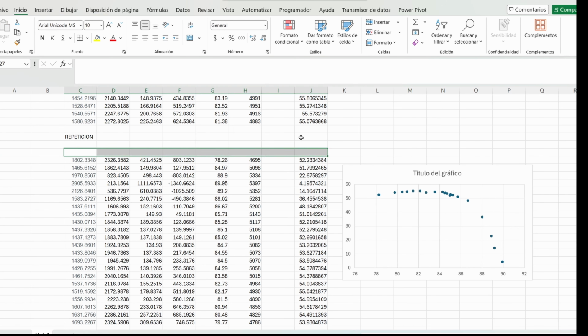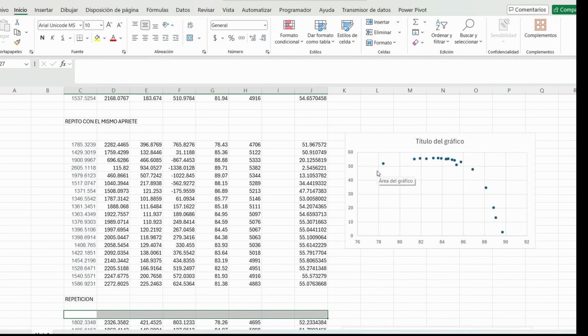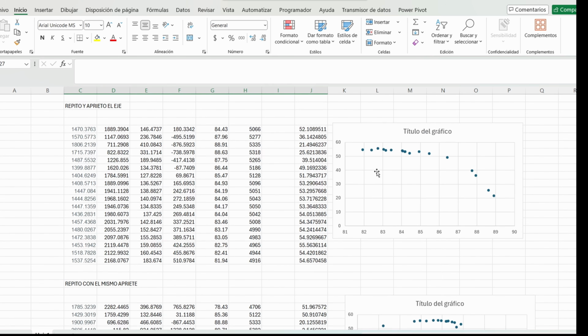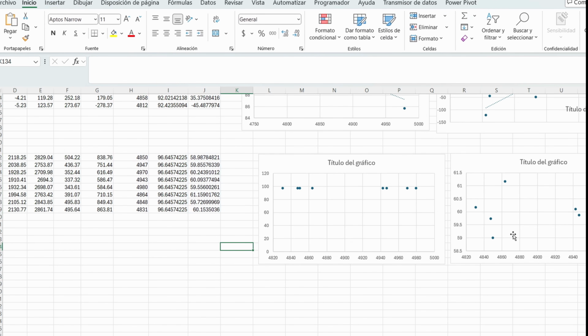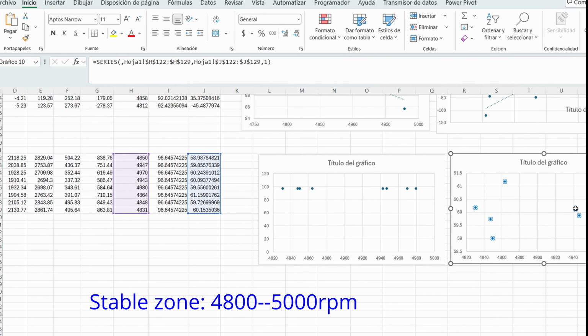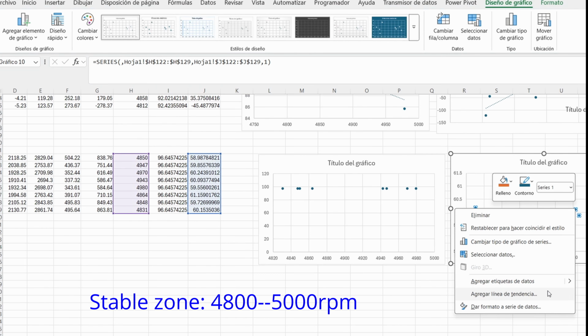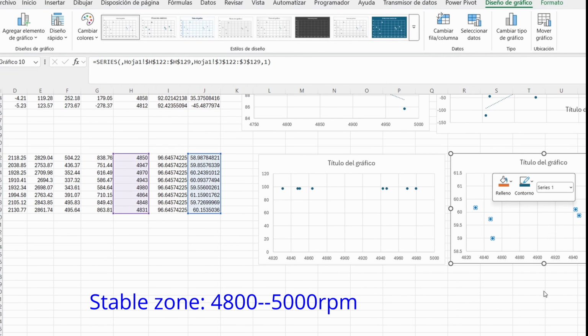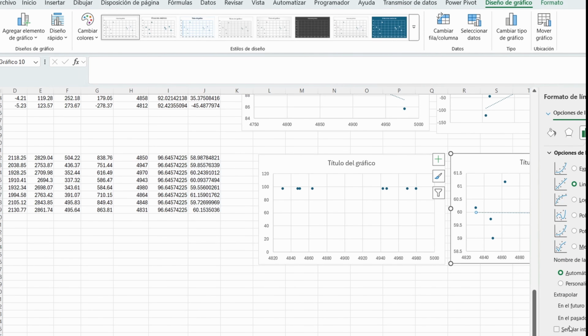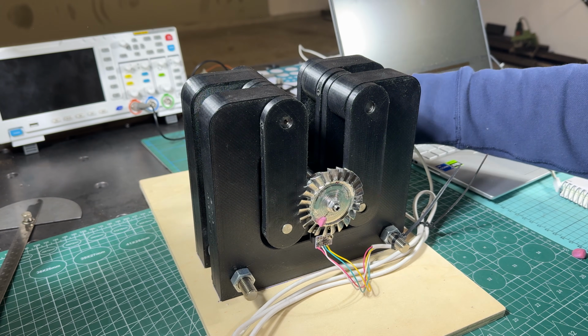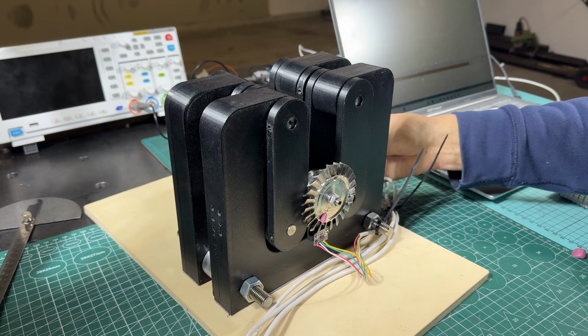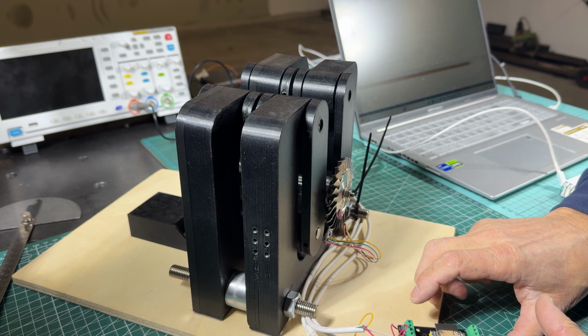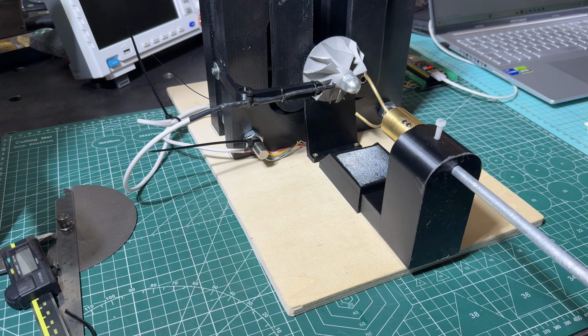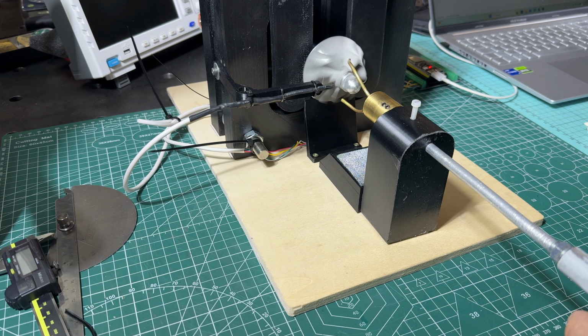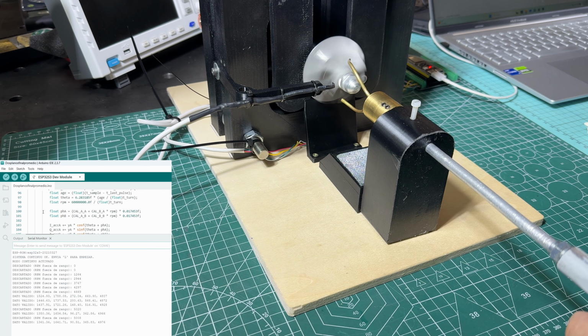Next step. Identify the most stable measurement window. Measurements near structural resonances are useless. After testing multiple RPM ranges, I found that between 4,800 and 5,000 revolutions per minute, the system response was highly repeatable and free from resonance amplification. With stable measurements, I moved to system offset calibration. I placed a known mass at 0 degrees and measured the detected angle. The difference is the system phase offset.